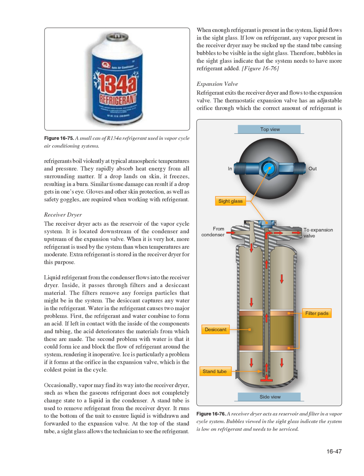When enough refrigerant is present in the system, liquid flows in the sight glass. If low on refrigerant, any vapor present in the receiver dryer may be sucked up the stand tube, causing bubbles to be visible in the sight glass. Therefore, bubbles in the sight glass indicate that the system needs to have more refrigerant added.